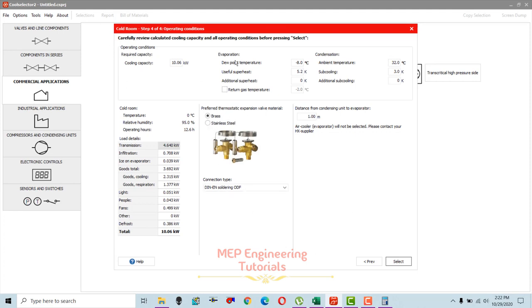Once you select next, you can see the load summary. The total required cooling load is 10.06 kilowatts. The cold room temperature condition is shown, and the refrigeration system will run 12.6 operating hours based on storage temperature and relative humidity. The different load components are listed: transmission load, infiltration, goods respiration, cooling, lighting, fan, defrost — totaling 10.06 kilowatts.